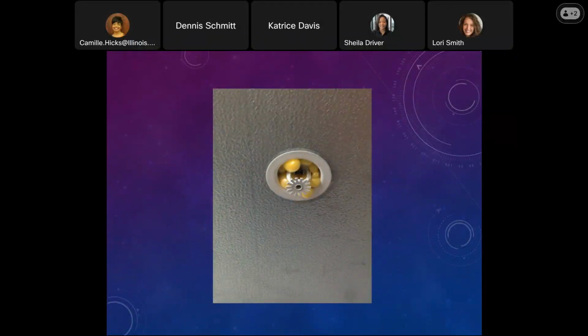This is a problem you may see: sprinkler heads sealed with expandable spray foam. This foam isn't intended for use in commercial construction projects for fire stopping. Actually, this material is combustible, you can set fire to it. So twofold, they're using the wrong sealant, and the sprinkler head is being impacted because the glass vial in there probably will not activate if a fire happens, which could impede the water source from coming out to extinguish the fire. So two issues with that.